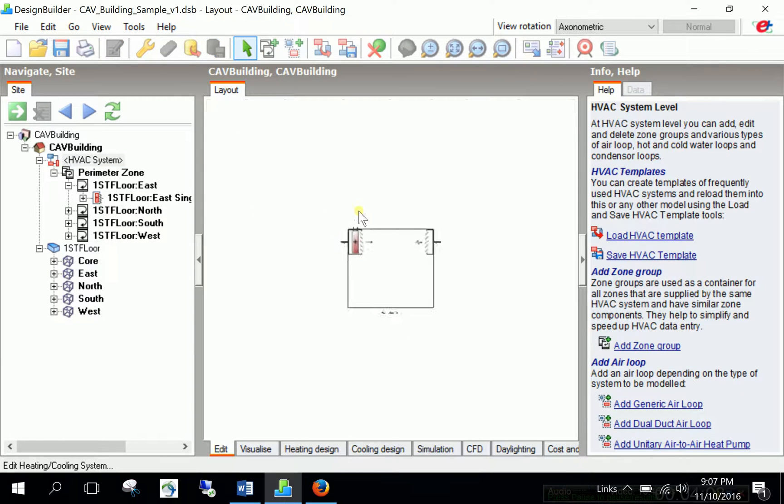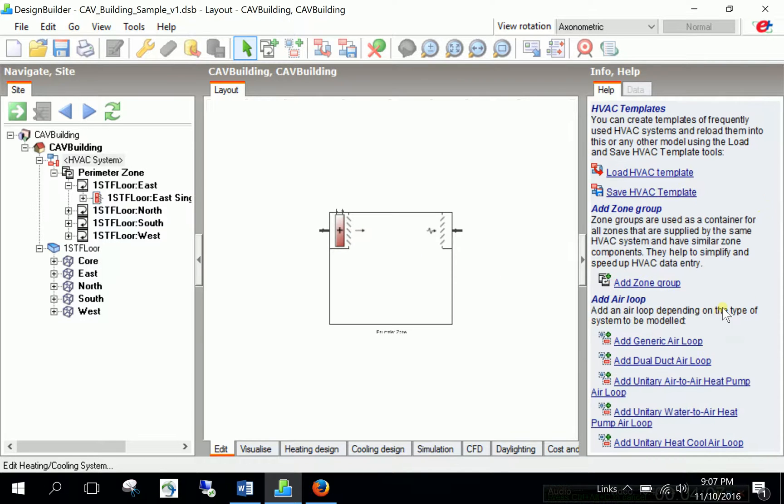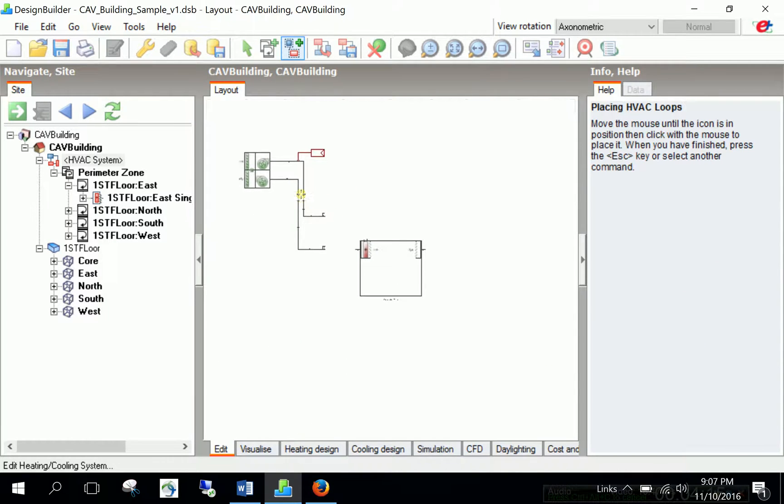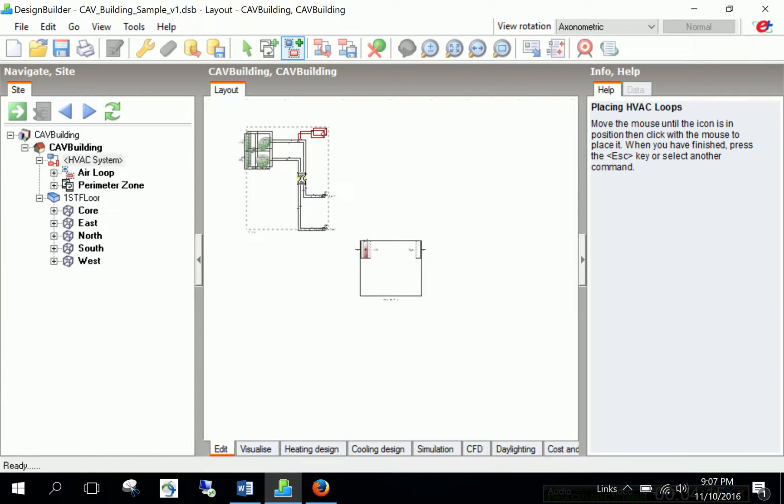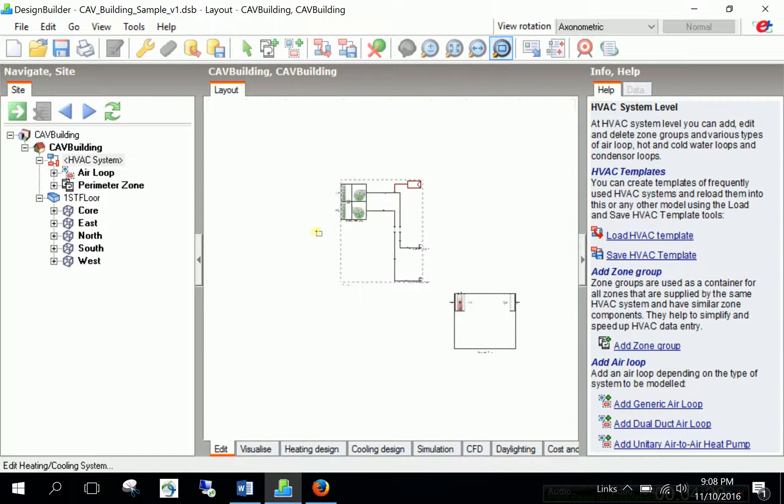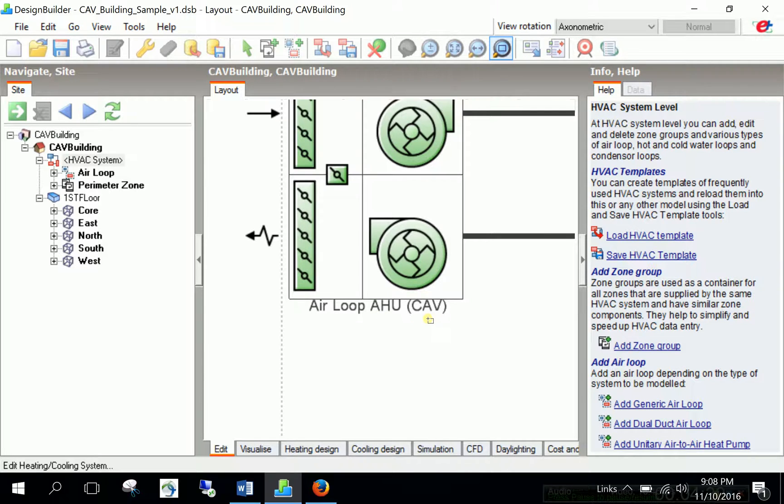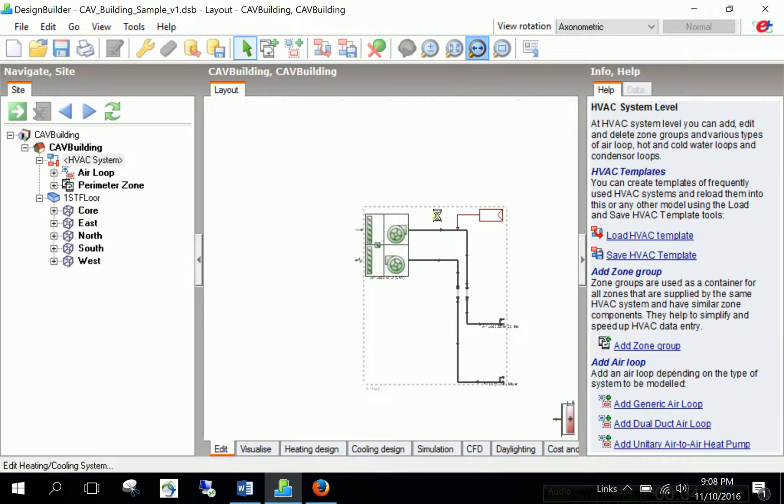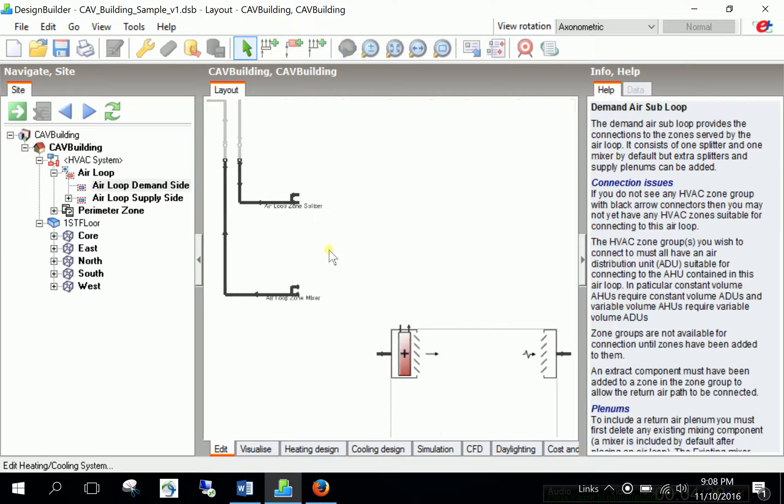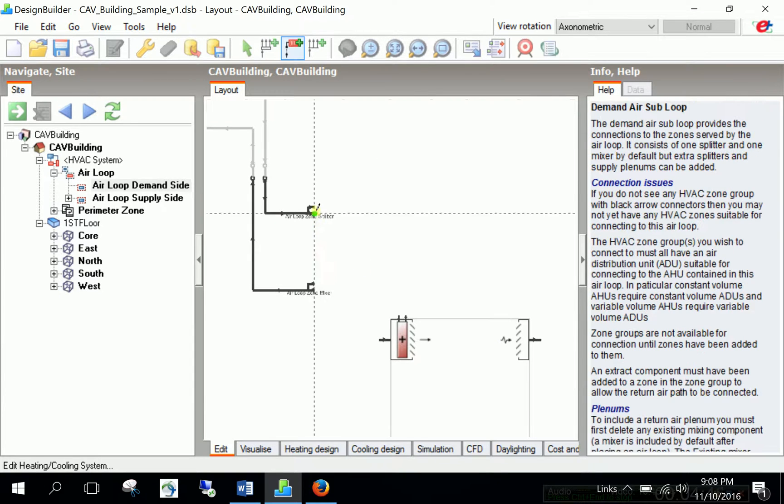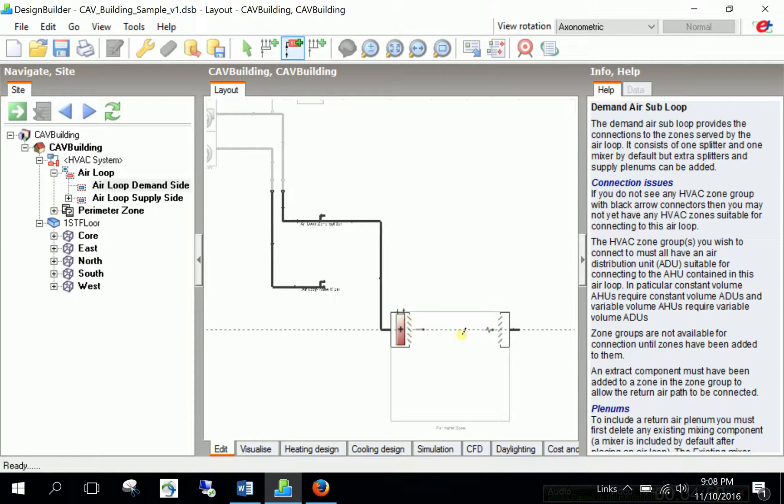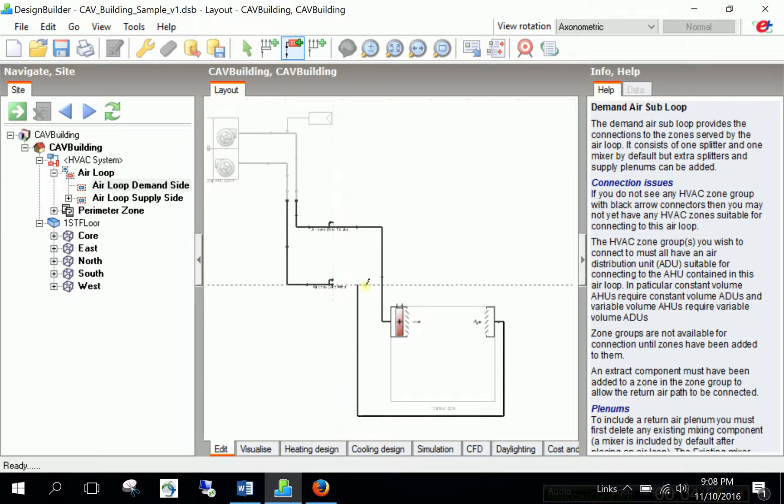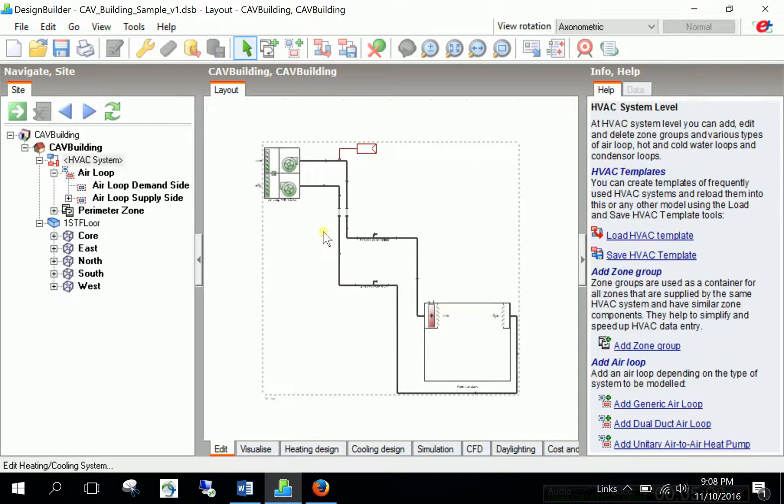So, now the terminal units are created. And I will go back to the main HVAC system tab. And now I have to add an air loop. And the air loop is generic air loop. Just click and drag and drop at some place in the canvas. And now we can see that it's added. Just have a closer look at it. It is air loop air to CAV. So, that's nice. No need to change the type because we are already doing CAV system. But we need to make the connections, right? So, you go to the air loop demand side and then scroll a little bit down and say connect components. Click and from splitter, I should go to the inlet of the reheat. And then from extract, I will just click and connect it to the mixer.